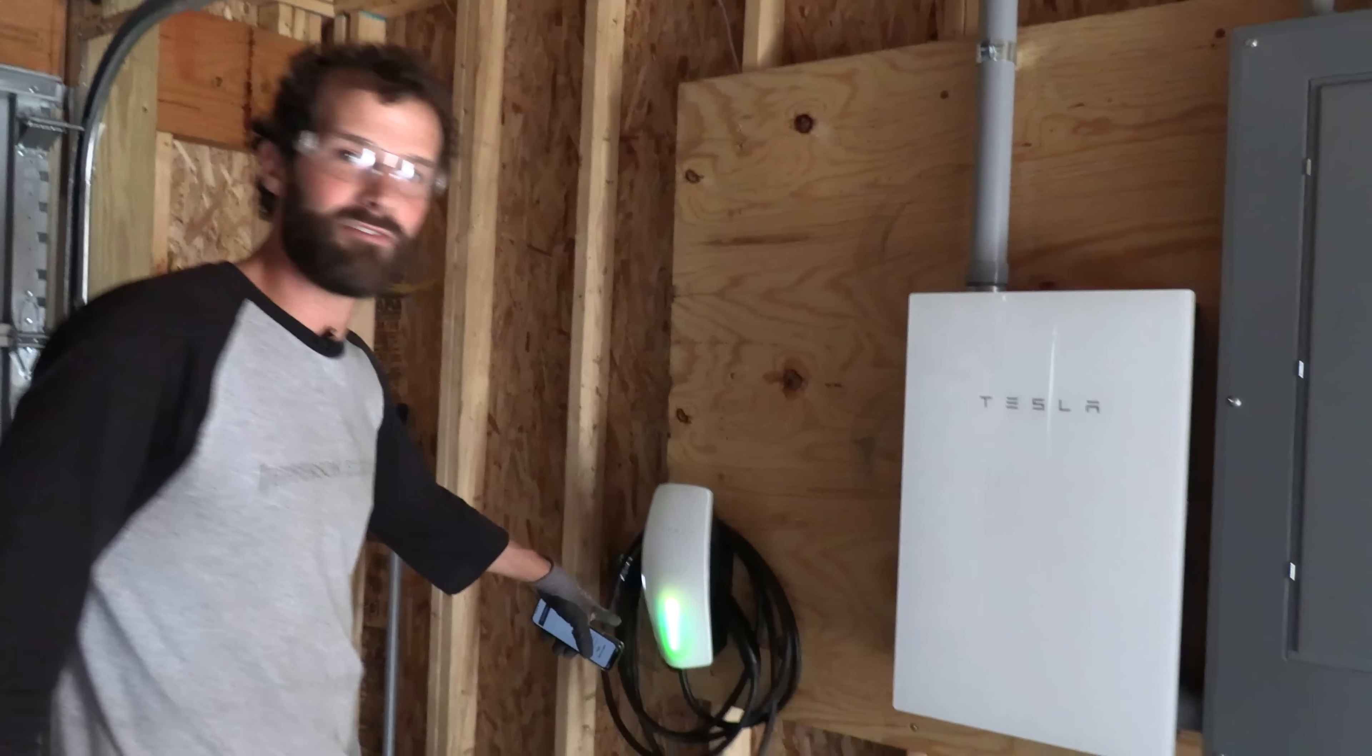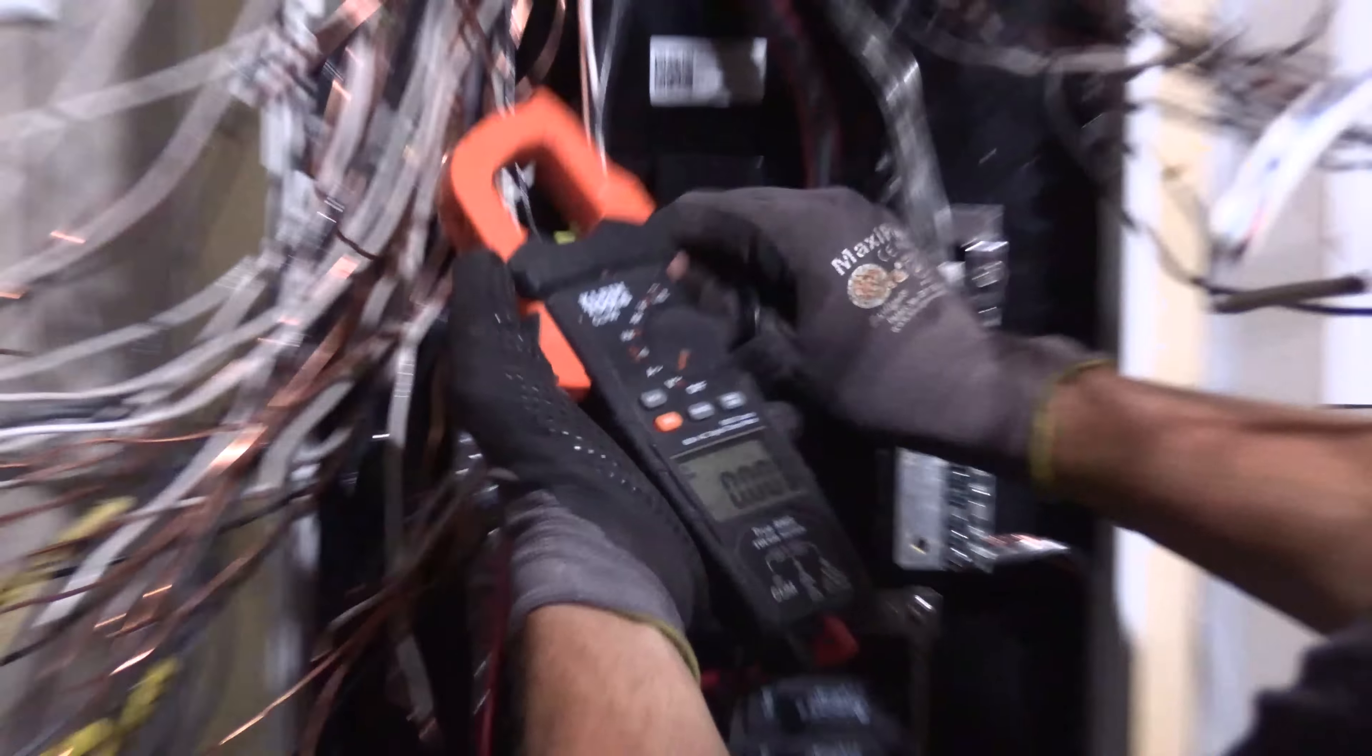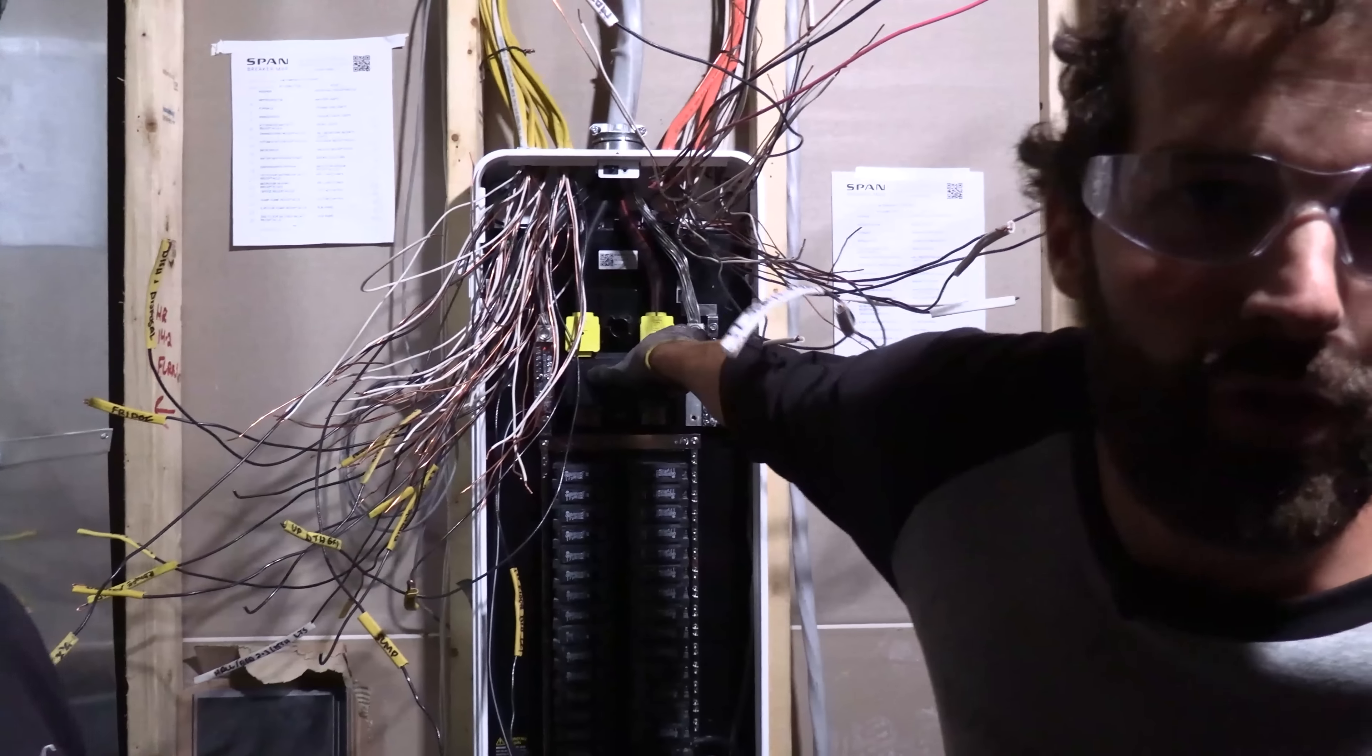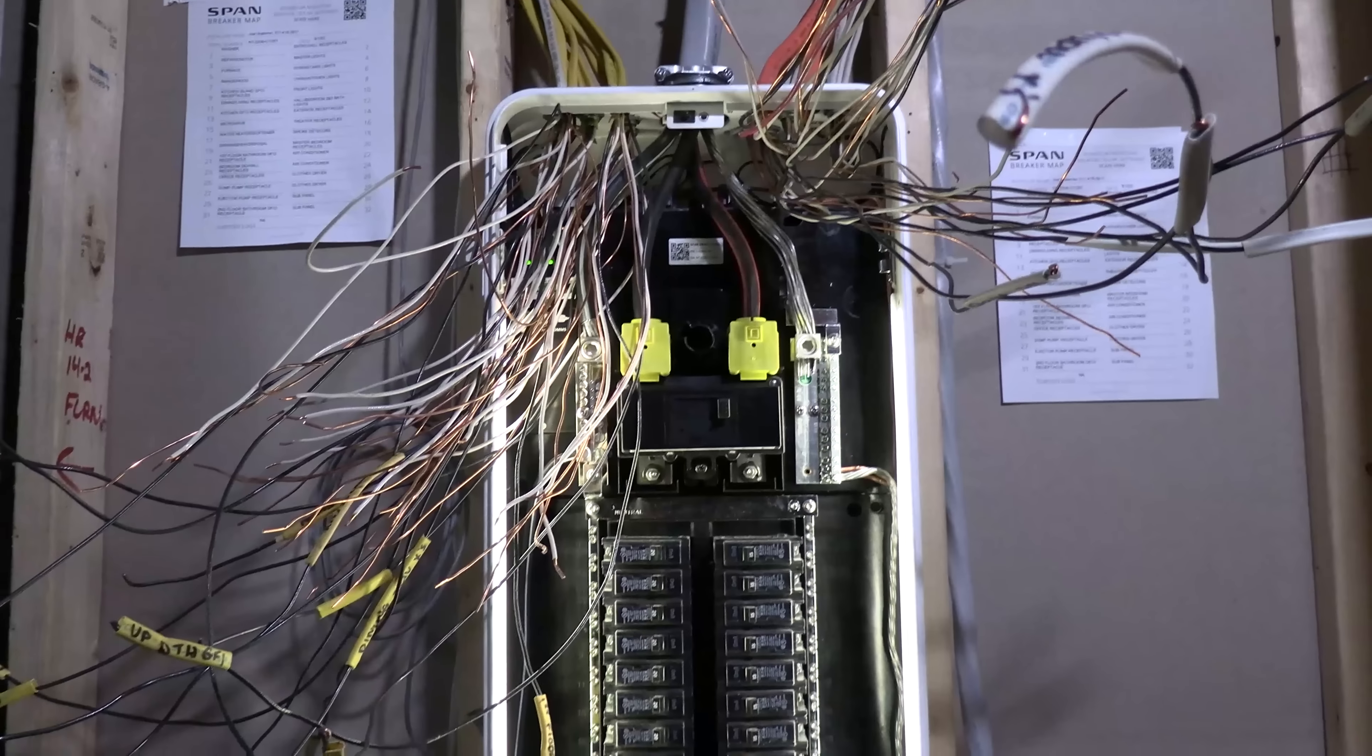Okay. We're here in the garage with the beautiful Tesla setup and I'm ready to throw the breaker, get power back onto the house. Cliff is expecting it. Hands are clear. Uneventful. Good. Wall connectors are coming back live. Two of them out here. It's an electric family. 242 volts. Let's check. We got it. Last thing we want to do is not have a neutral for some reason or be missing a leg. Sometimes when breakers are set, one of the legs doesn't connect. Look away. Oh, that's gorgeous. Fans are running.